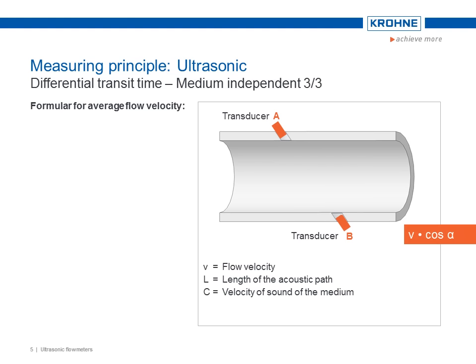Assuming, then, that neither temperature, pressure, nor composition of the medium change in such a short time, the resulting flow rate of the medium can be shown as follows. The length of the acoustic path divided by 2 times the cosine of alpha multiplied by the result of dividing the difference between the two transit times by the product of the two transit times.